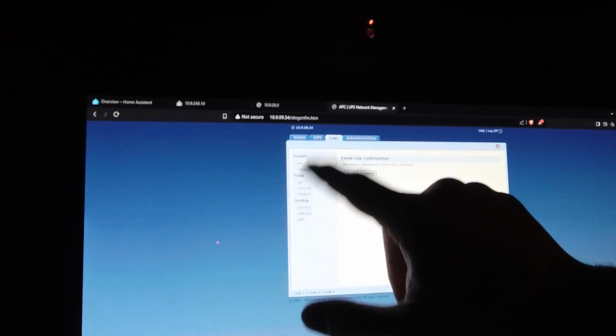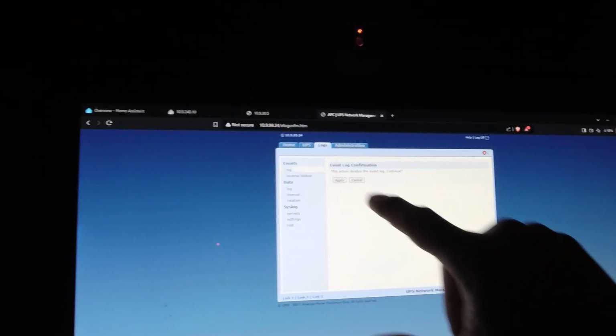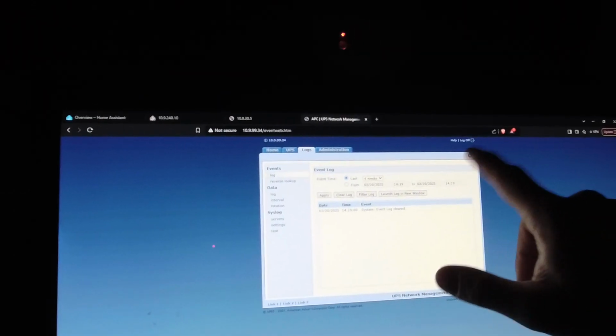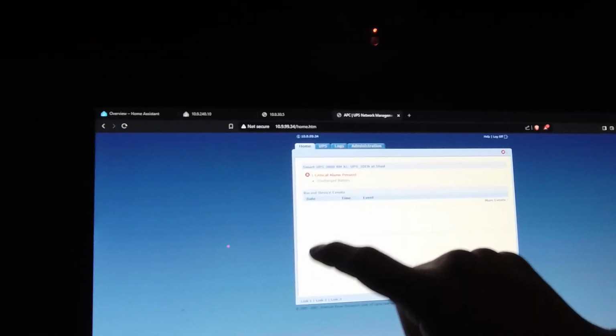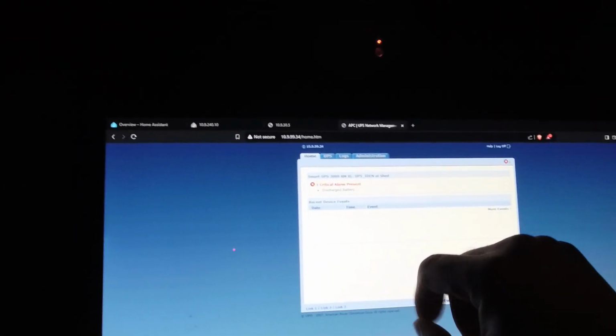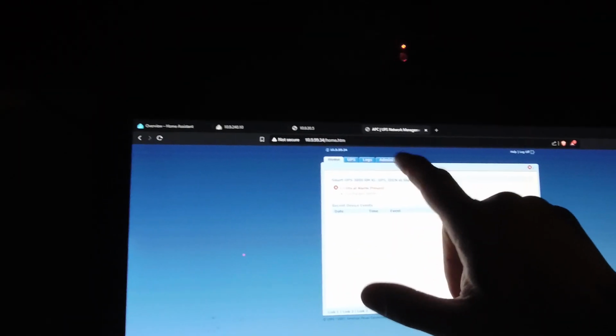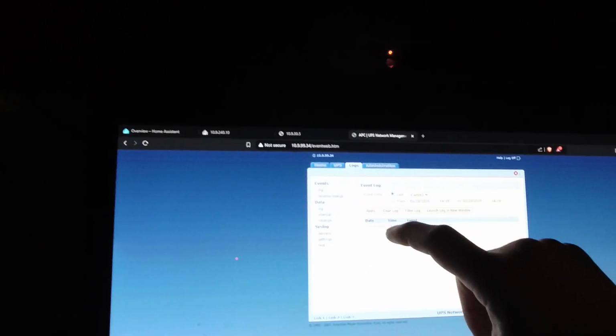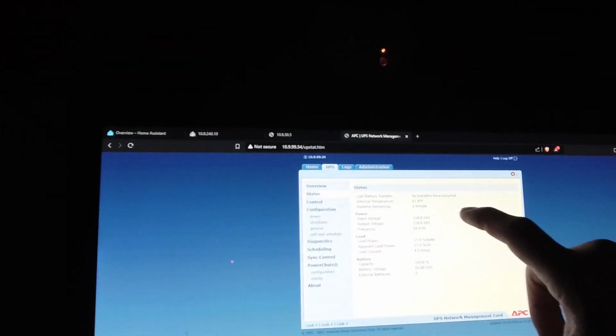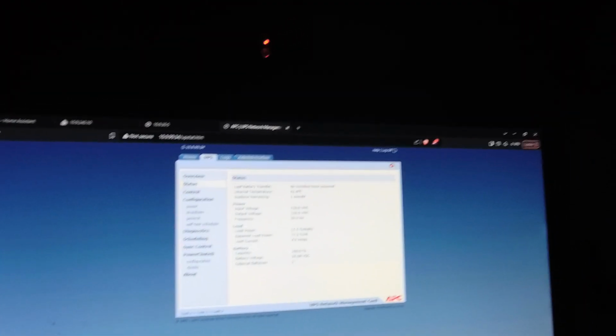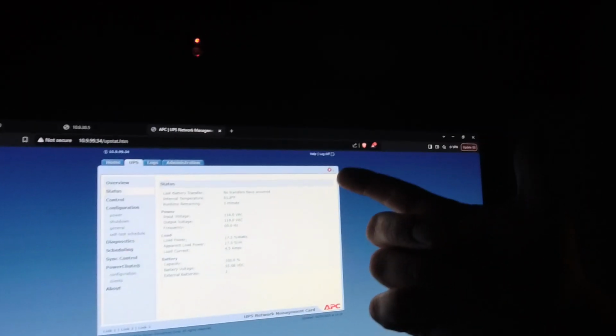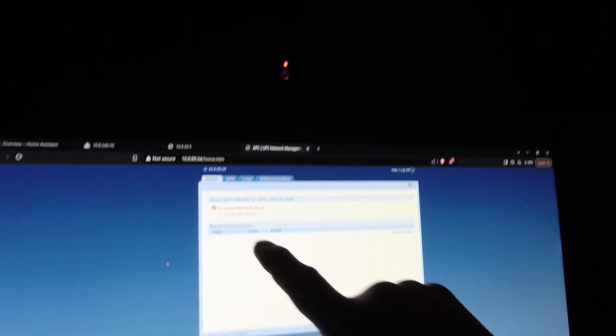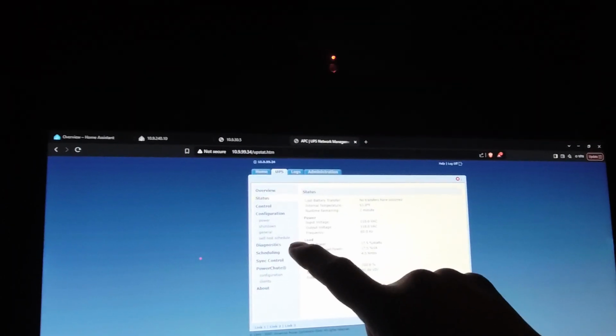Can we clear and acknowledge these alarms? Where do we do that? Come on, somewhere in here we got to be able to acknowledge that alarm and tell it to go away. Or reset the... I bet you we have to do like a runtime calibration in order to satisfy that and make that go away. Probably. Discharge battery, but it's not.